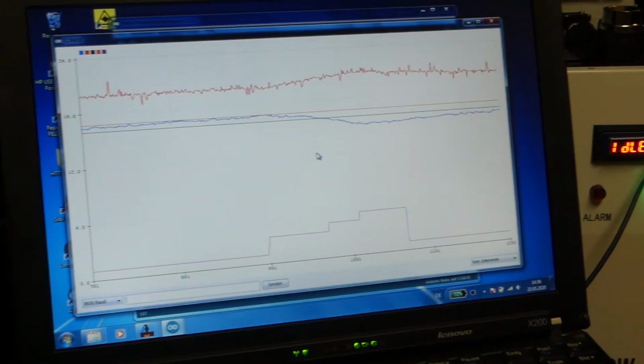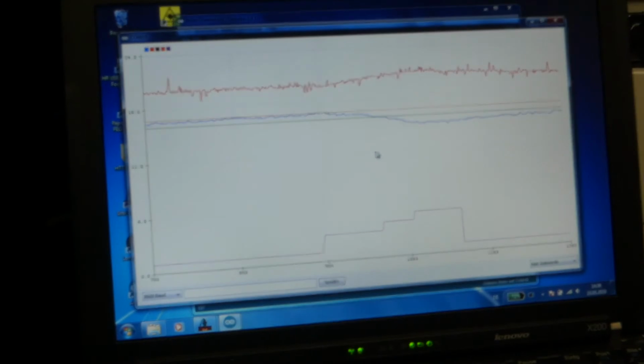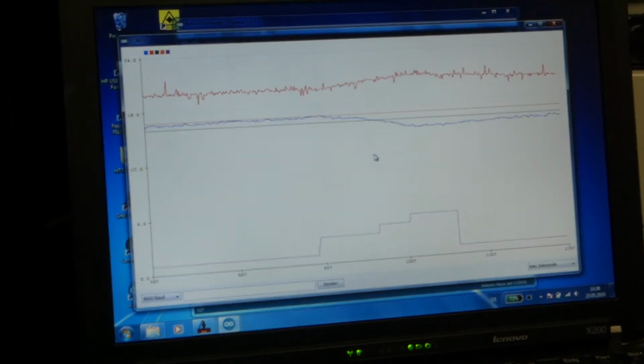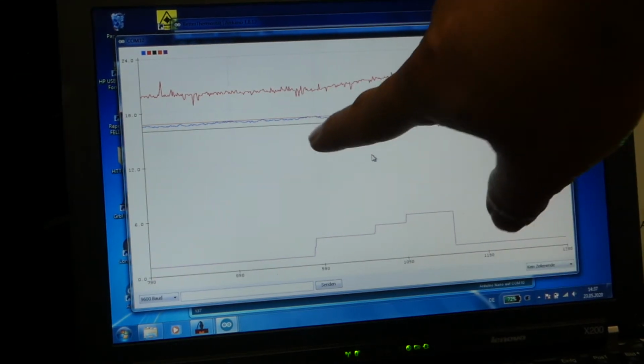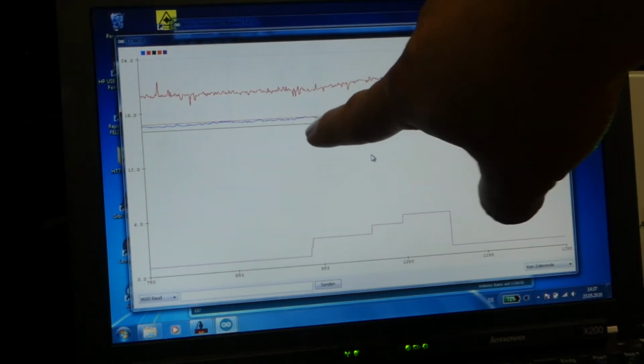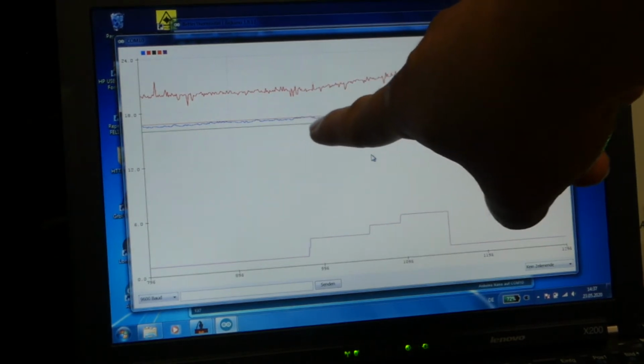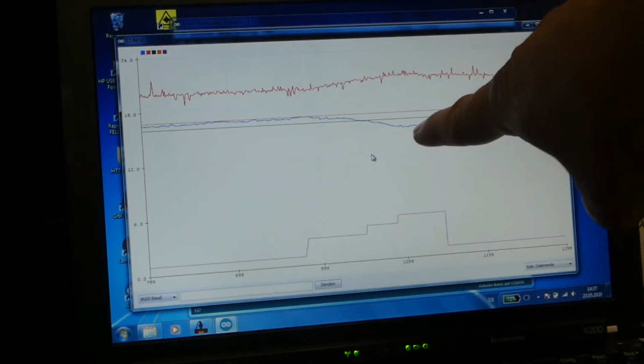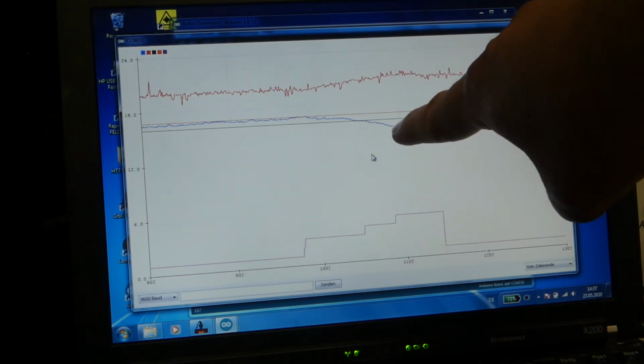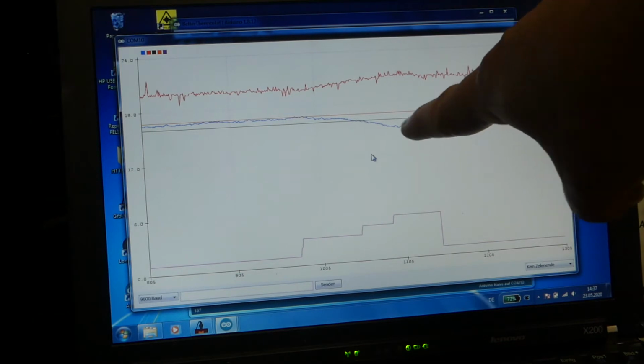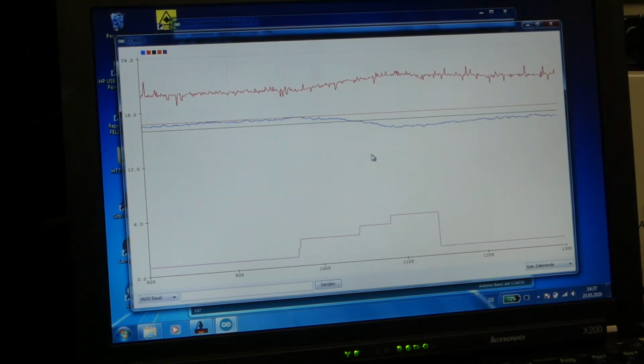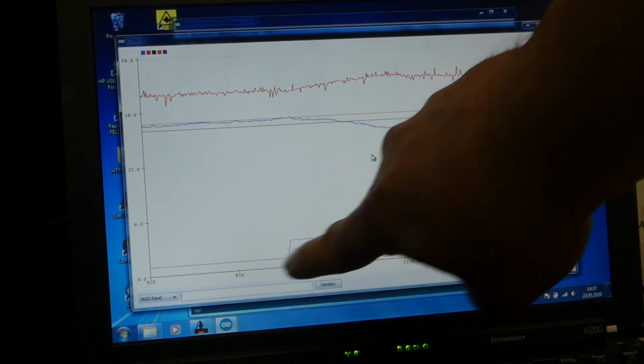If we take a look at the curves that are recorded during the cooling, you can actually see that it warmed up to the hysteresis point over the set 16 degrees. Then it cooled down pretty quickly, and it stopped cooling right about at the hysteresis point below the 16 degrees, which is pretty much spot on where I want to have it. And now that it's cooled down, it is holding very well. And you can actually see that it went through all the stages of cooling.